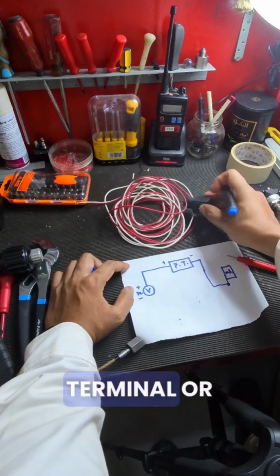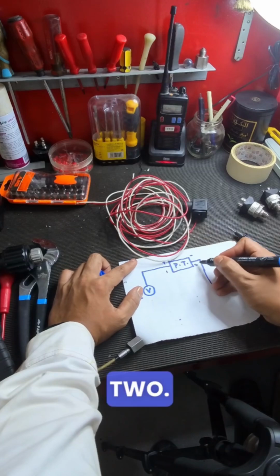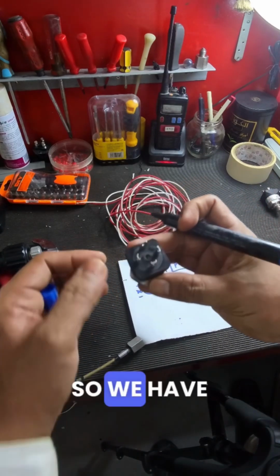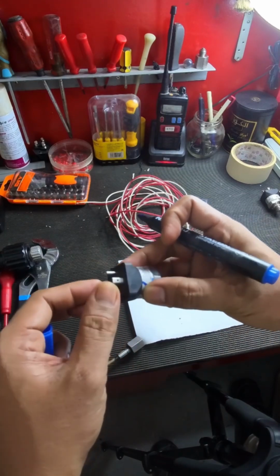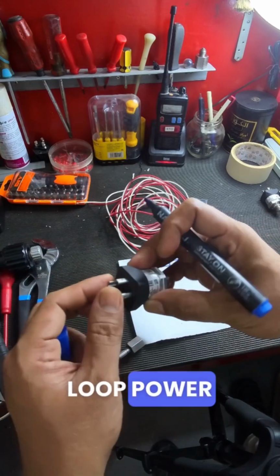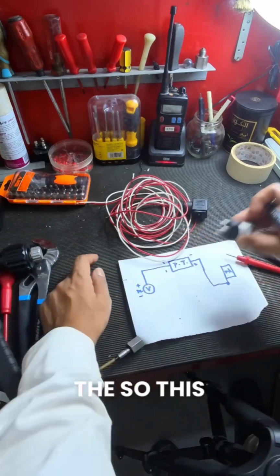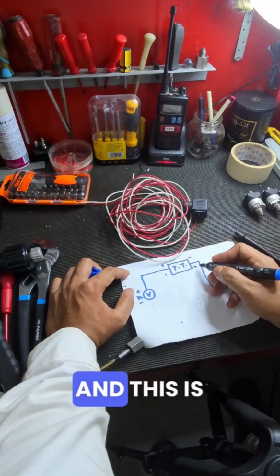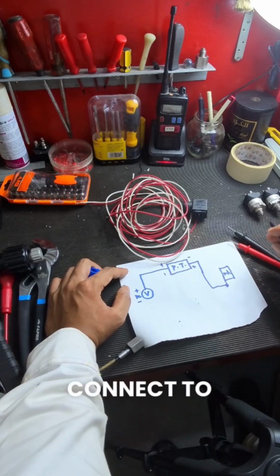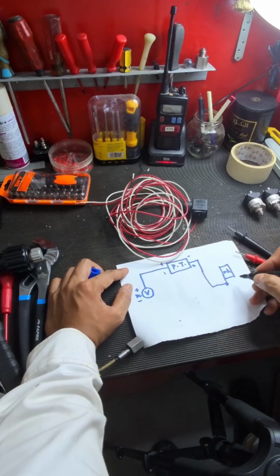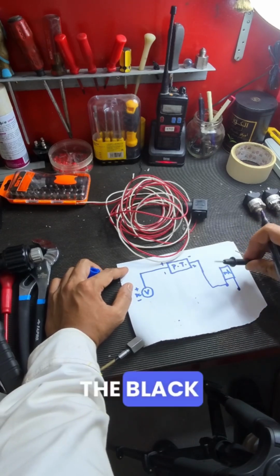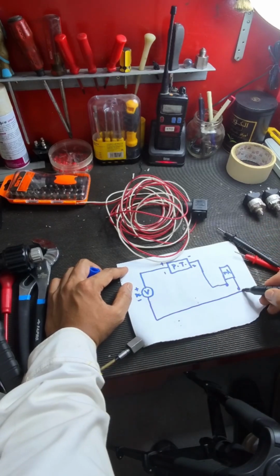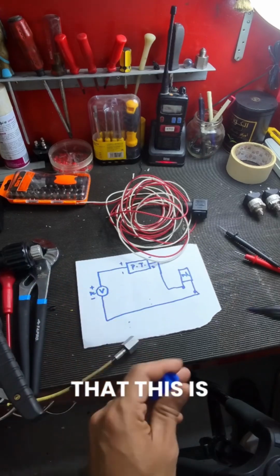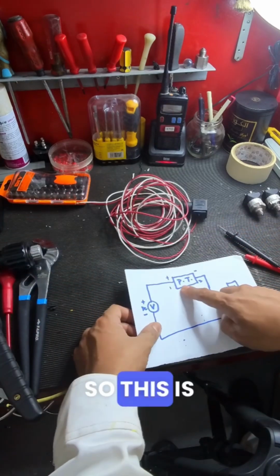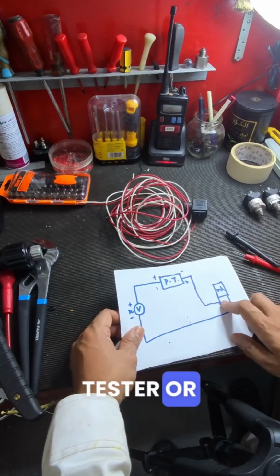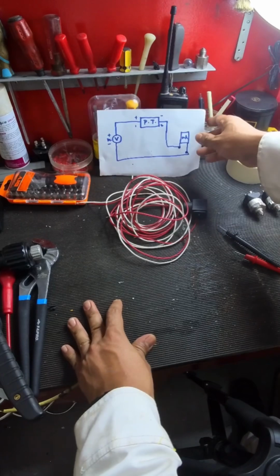In the plug, or the terminal or connector, this is number one and number two. We need only two connections for this 4 to 20 milliamp loop powered pressure transmitter. One is the positive and two is the negative. The positive one and the two from the pressure transmitter go to the red probe of the multimeter, and the black probe connects back to the negative source. Simple as that. This is a simple loop circuit, a series circuit. This is the load, and this is the multimeter, or milliammeter, that can read DC milliamps.